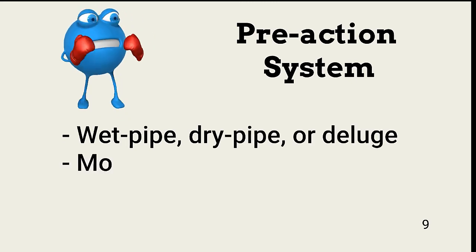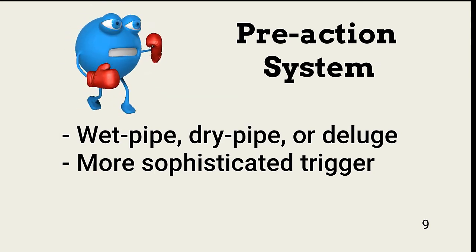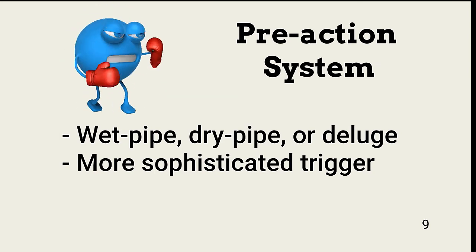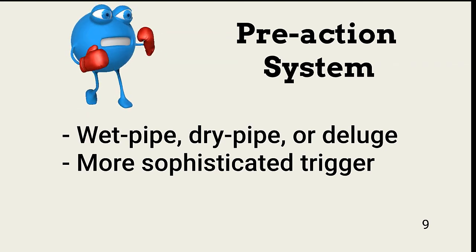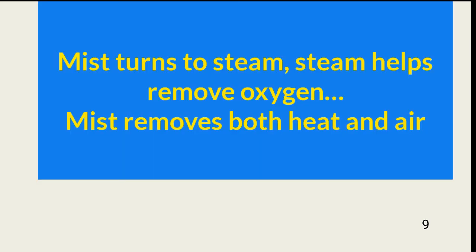Pre-action systems have an extra step in the distribution of water. For example, a pre-action dry pipe system would have an initial trigger that fills the pipes with water, but the water would not be released through the valves until an additional trigger occurred. Any of these water systems can also have a sprinkler head that creates a mist as a delivery mechanism. In addition to removing heat from the fire, the steam created when the mist reaches the fire also displaces oxygen, so mist delivery systems remove both air and heat from a fire.